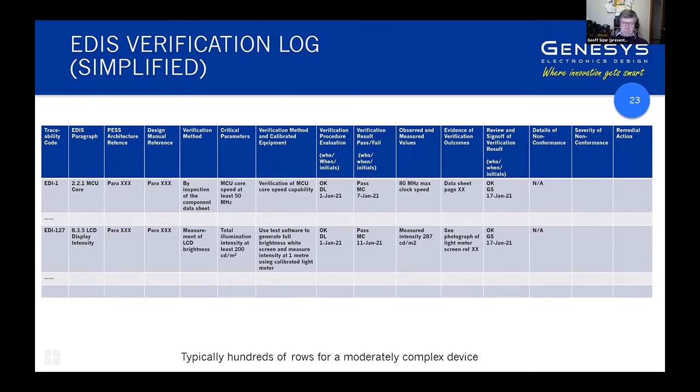So you then have, I've got a question here, sorry, from Matt Sheedy asking, does hazard and risk analysis, i.e. ISO 14971, impact on the rigor and depth of effort you would apply to verifying and validating requirements and or the design aspects of the medical product? I'm not sure if that question was a general one or relating to how that would get down to this level. It absolutely does.